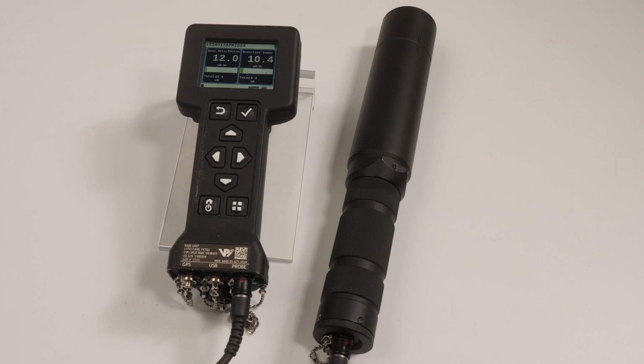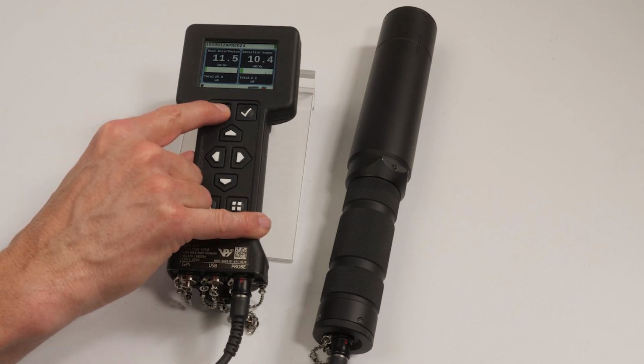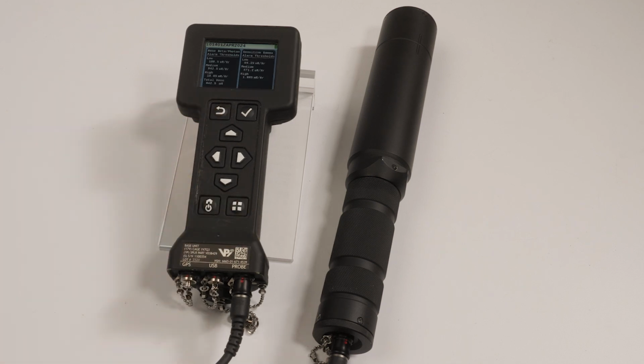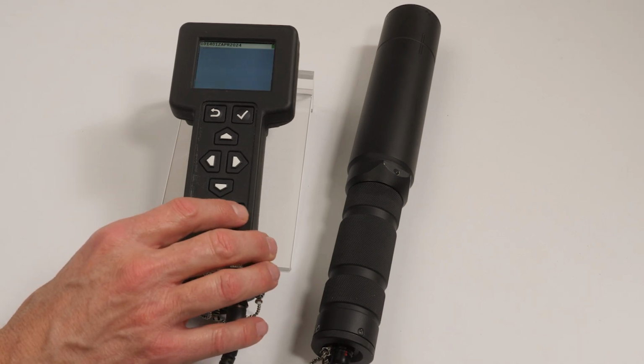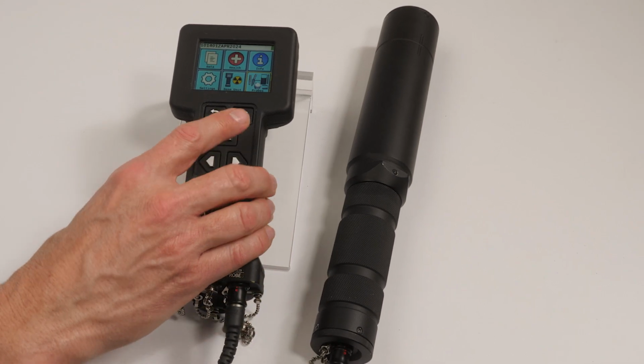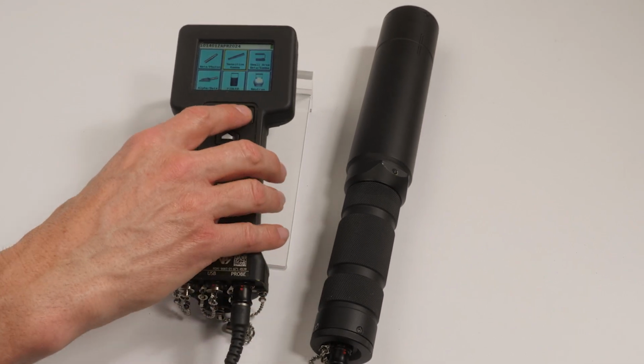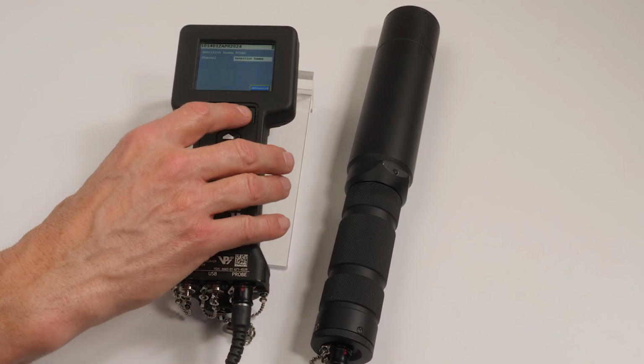While on the home screen, press the back key to display the alarm thresholds. If you need to change the alarm thresholds, you can go to the main menu, select Probe, choose the sensitive gamma probe, and go to the advanced screen to make changes. Before starting your survey or mission, you should verify the probe is working as expected by performing a source check.